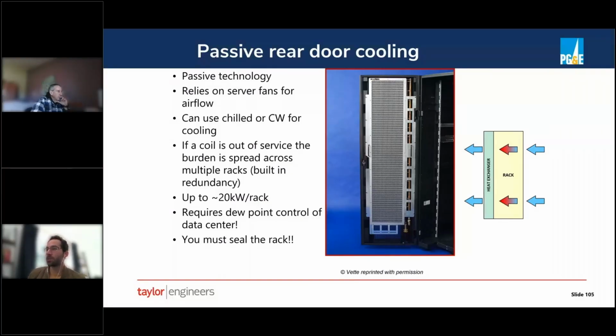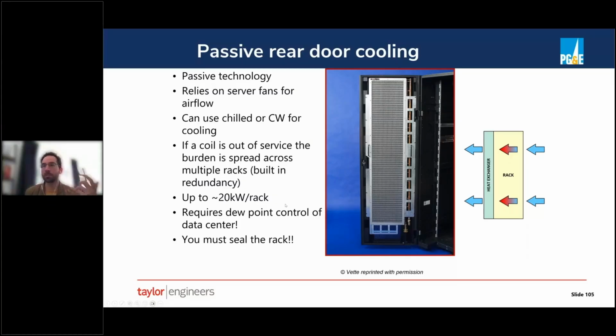The cooling medium can be either chilled water or condenser water, depending upon the application and what your design ambient conditions are, as well as the supply air temperature or the cold aisle temperature that you need for your application. When a coil is out of service with this design, effectively that just means that the load is spread across the remaining rear doors within the data hall. So there's built-in redundancy. Typically, we've seen this strategy be effective at up to 20 kW per rack. Anytime you go above that, you tend to get in the territory where an active rear door approach makes more sense. One of the key things with rear door is you need to make sure you have dew point control within the data center. And I'll talk about that in a second, and then I'll explain why that's necessary.